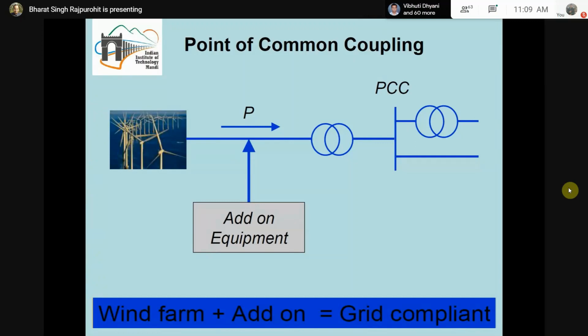This should be very clear, because in India every state has a different definition of point of common coupling, which needs to be addressed. Then individual wind farms can be augmented to meet the grid codes. Otherwise, additional add-on equipment can be added, known as FACTS devices, STATCOM, or a simple capacitor bank, so that such grid codes can be met. So these are the technical requirements.